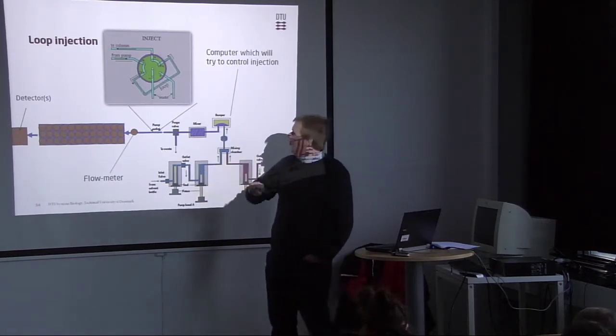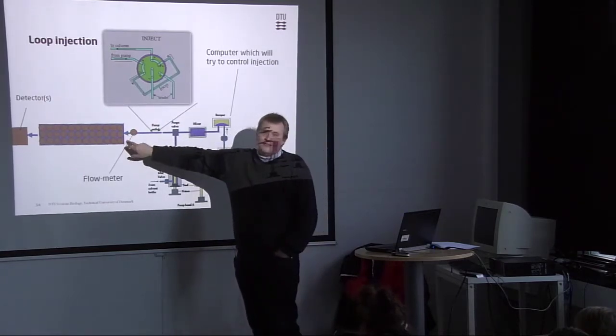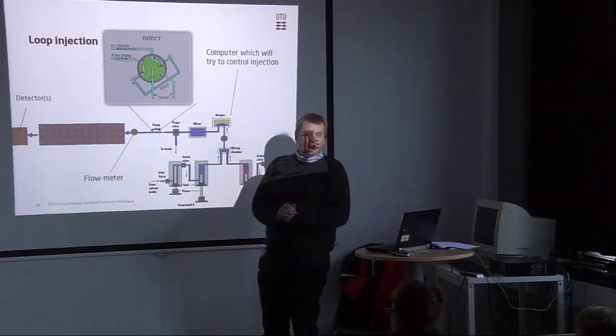There can be some columns where you need to have a certain amount of organic solvents. So, you type in the software, say, a normal reverse phase column, you would type in maximum 300 bars. If the pumps need to give more than 300 bars to give the flow rate you want, the computer will shut down the system. You can also type in, usually in the software, a minimum pressure. You know that it takes a certain amount of pressure to go through the column. So, if it suddenly goes to one bar, you know something is wrong, the computer shuts down the instrument as well. But remember, it's flow controlled, so also if this one dies, the computer will get confused and nothing will work.